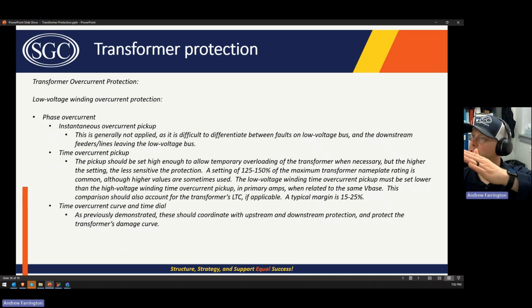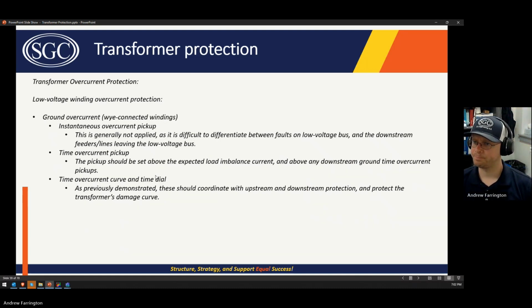No, vice versa. I had it right the first time. Low side, you want it to be less than the high side because it'll make the low side tend to operate faster. Because you want the low side to operate first for a fault that's out of section. So say the transformer is backing up an adjacent line relay, you want that line relay to operate first, then you want the transformer low side to operate, then you want the transformer high side to operate last. So generally you want the low side to be set somewhat lower than the high side.